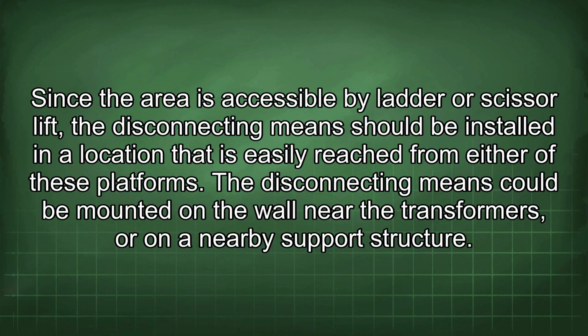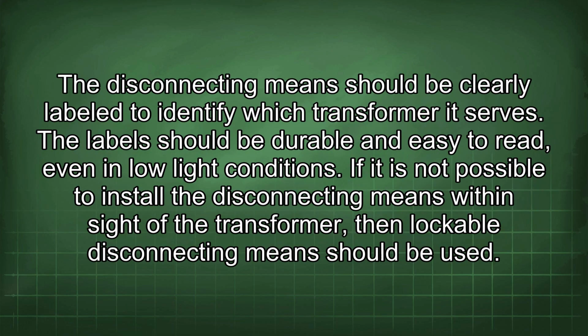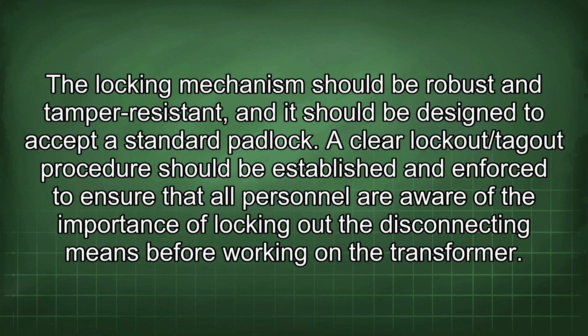The disconnecting means could be mounted in the wall near the transformers, or on a nearby support structure. The disconnecting means should be clearly labeled to identify which transformer it serves. The label should be durable and easy to read even in low light conditions. If it is not possible to install the disconnecting means within sight of the transformer, then lockable disconnecting means should be used. The locking mechanism should be robust and tamper resistant, and it should be designed to accept a standard padlock.